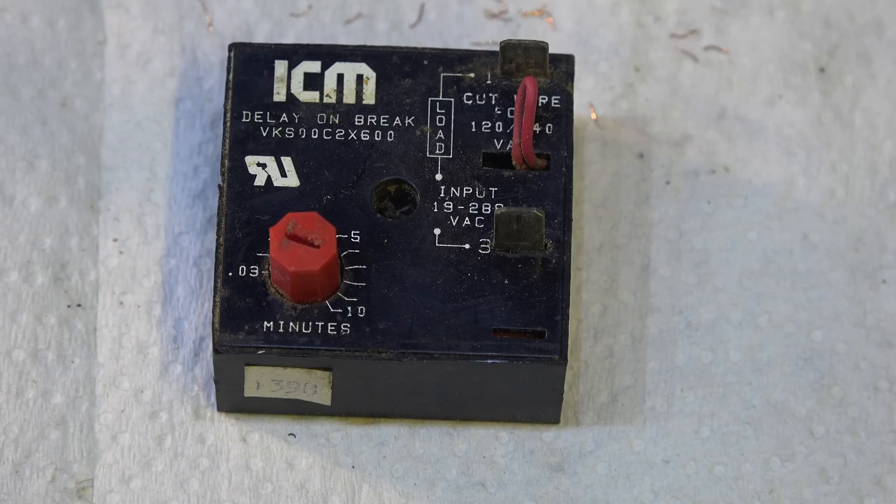A lot of units already have it. Thermostats have a non-recycle option on most electronic thermostats. Some units have time delay. The whole idea here is to give the compressor time to equalize its pressures and then it can start easier.